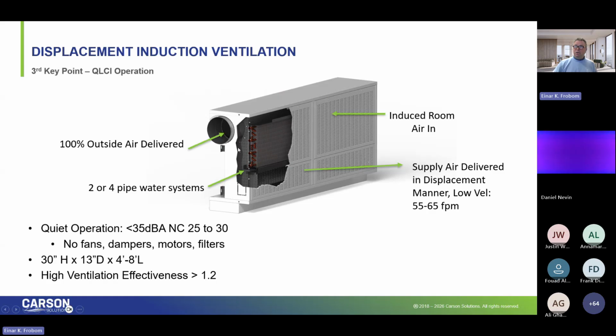And it's that low pressure creation that induces 2 parts room air for every 1 part of fresh air that I deliver. So if I, in a typical classroom, deliver 400 CFM of outside air to our diffusers, we will induce 800 CFM of room air that travels across the singular hydronic coil that can be either 2-pipe or 4-pipe. That room air gets heated or cooled based upon the fluid that's in that coil, mixes with the fresh air. And now in my example, those air streams mix, and now I have 1,200 CFM of reconditioned supply air out to the space, moving at a very low velocity.